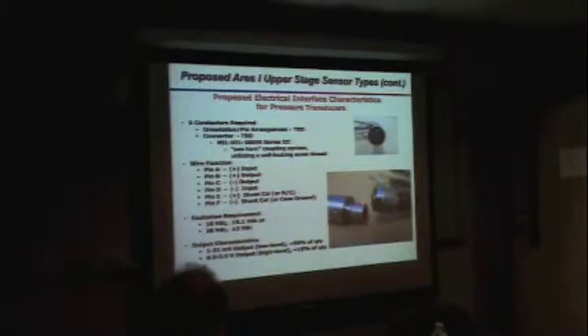As you can see right here, it's threaded, and this connector kind of clicks and locks when you put it in place. This particular connector is for a pressure transducer, and there are 6 pins. Here's the function of each pin. Now down here you see this is called a shunt calibration. You take a resistor and shunt it into the system so that it generates like 70% of the full scale output measurement, so that you can get an idea that the sensor's still working, still alive.